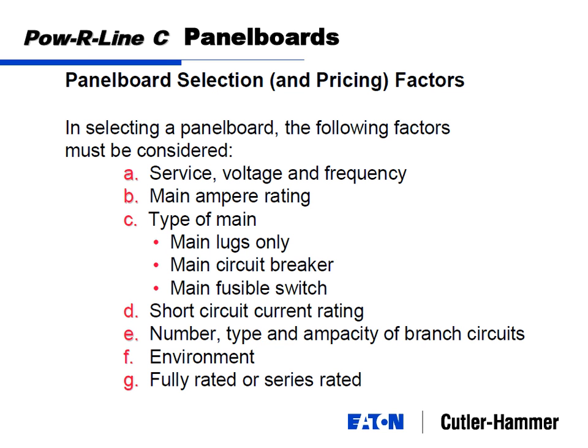The other thing is environment. By default, everything that we provide is going to be what they call NEMA 1. It's going to be indoor rated, and that's about it. If different environmental factors come into play, those also need to be accounted for in the panel board. So for an outdoor application, they have what they call a NEMA 3R, which protects against rain coming down. But if you read how the protection works, it doesn't protect against rain coming sideways or a hose going sideways. Then you move into other classifications. There's a classification called NEMA 12. NEMA 12 is dust type.